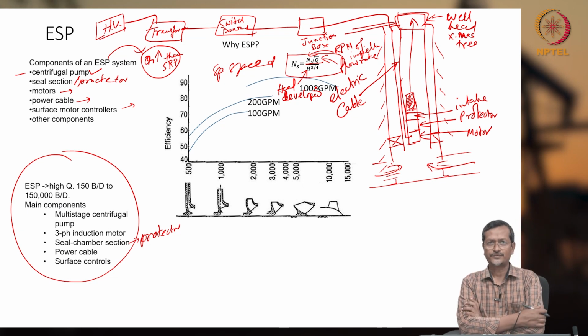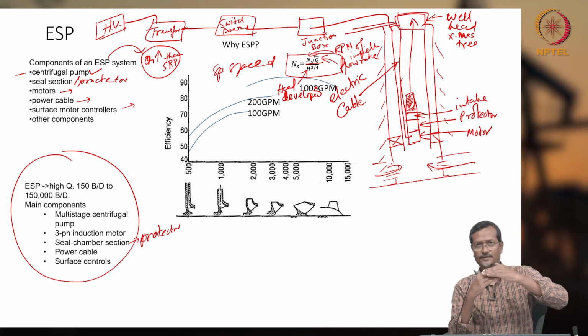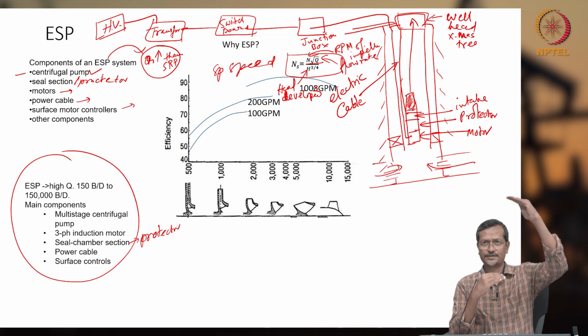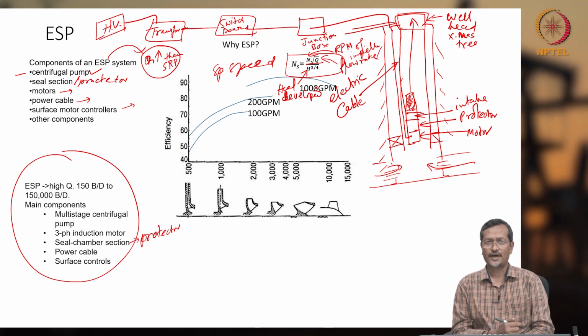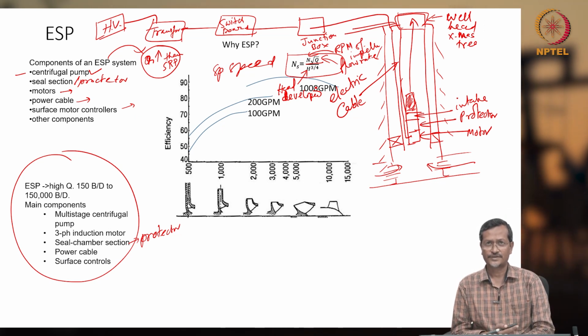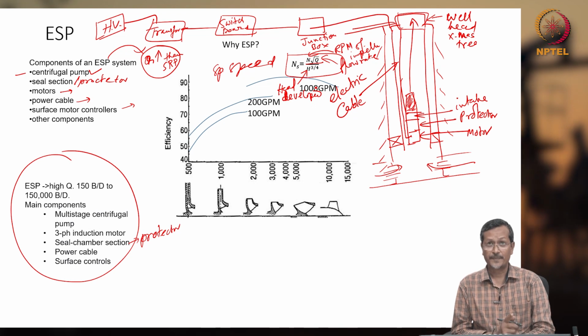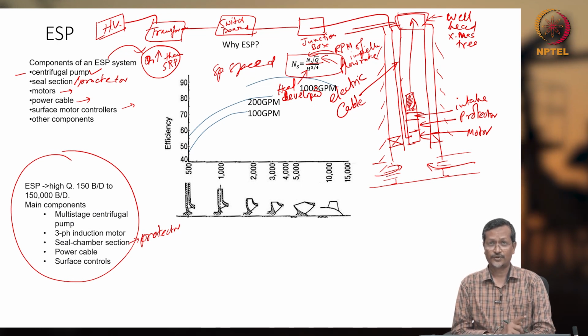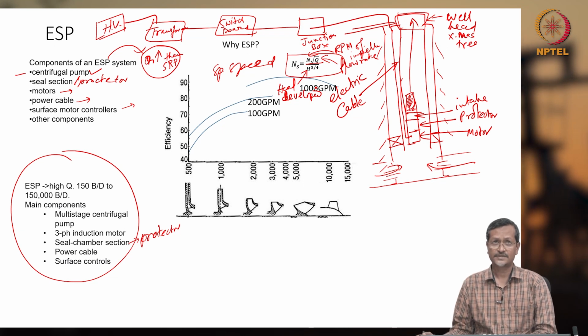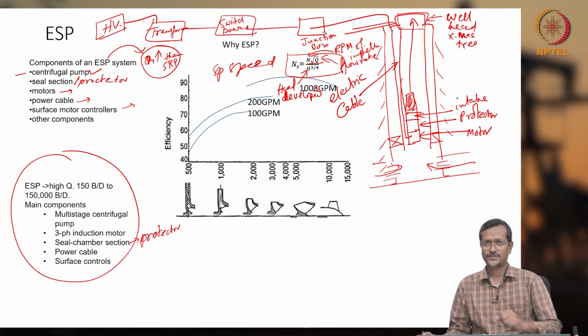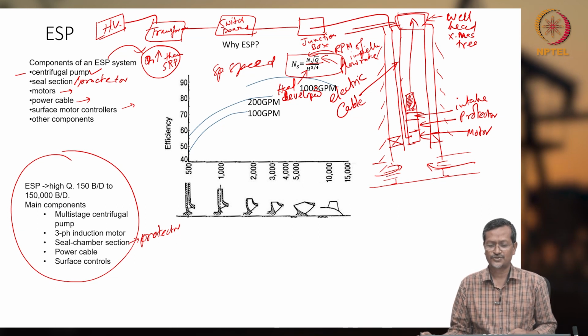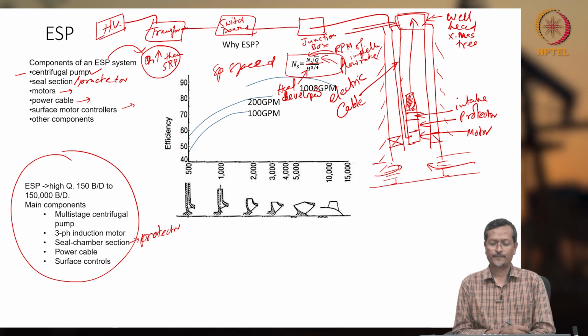Okay, so how much fluid it is creating, how much head you are developing, that is H, and how much flow rate you are giving, that is Q, and N is the impeller speed. Okay, it is not the motor speed, maybe the motor speed will be higher, but the impeller speed will be lower because of slippage, or maybe some other losses may be there, and that speed can also change. Now, this specific speed is actually not a non-dimensional number, it has a unit.